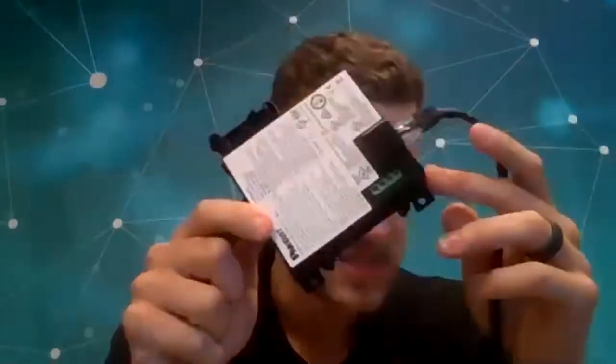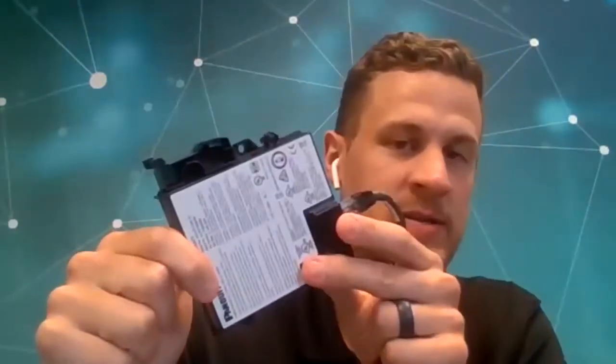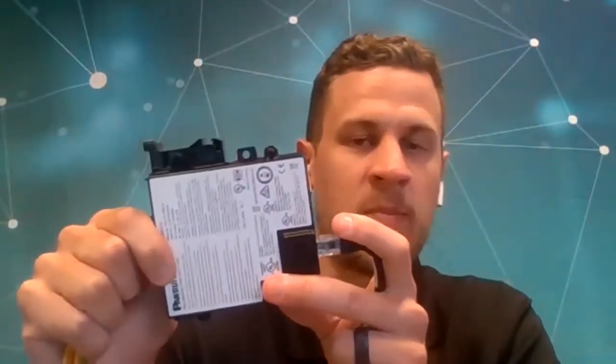The second component is your system cable, and it's kind of hard to show here because it's an 8-foot system cable, but this is what's going to connect you from your indicator module to your isolation module, or the brains of the AVT. This isolation module is the functional safety rated portion of this product. It's got redundant circuitry and it's fail safe. So you'd have to have two separate failures occur for this to give you a false indication. In layman's terms, you could press this button for 1,000 years and you never get a failure based off of our calculations with our functional safety certification.